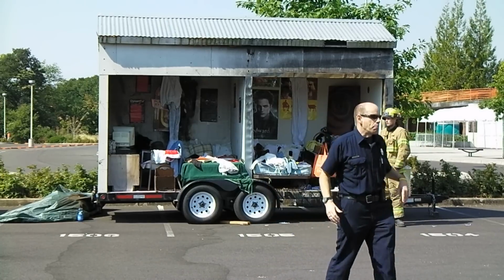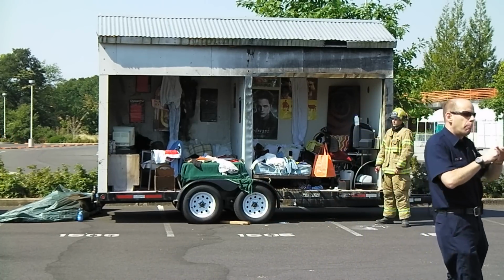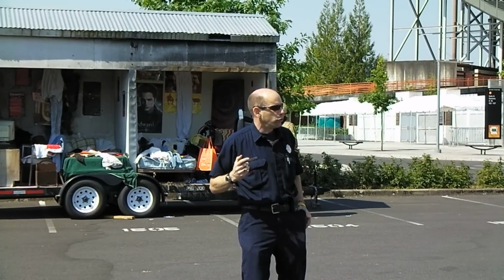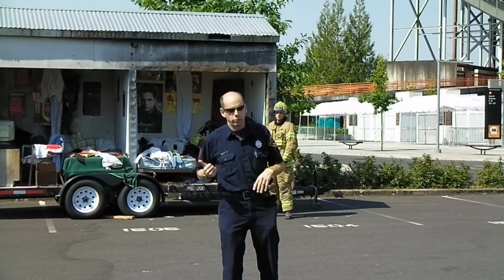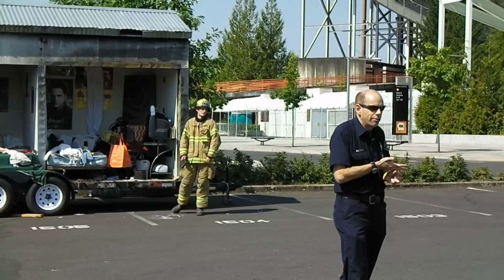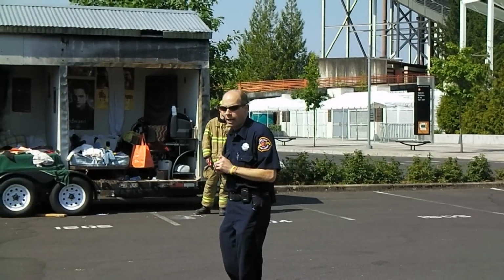Sorry about that. The room on your left has a single sprinkler head. Both rooms have a smoke detector, so they'll go off at different times. I want you to observe how quickly the head on the left goes off. It's a residential head, typical of what you would expect to see in a resident hall, so it's not unusual in any way. So I want you to pay attention to that too.